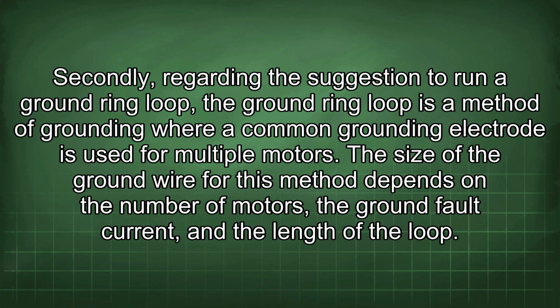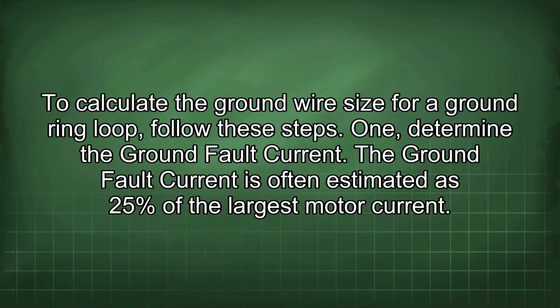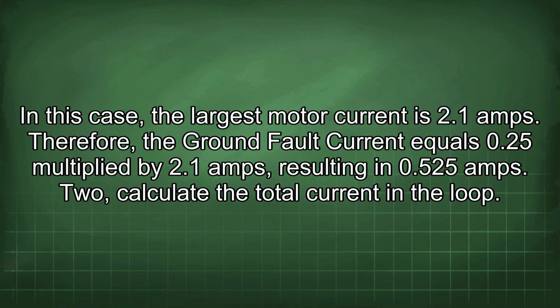The size of the ground wire for this method depends on the number of motors, the ground fault current, and the length of the loop. To calculate the ground wire size for a ground ring loop, follow these steps. 1. Determine the ground fault current. The ground fault current is often estimated as 25% of the largest motor current. In this case, the largest motor current is 2.1 amps.